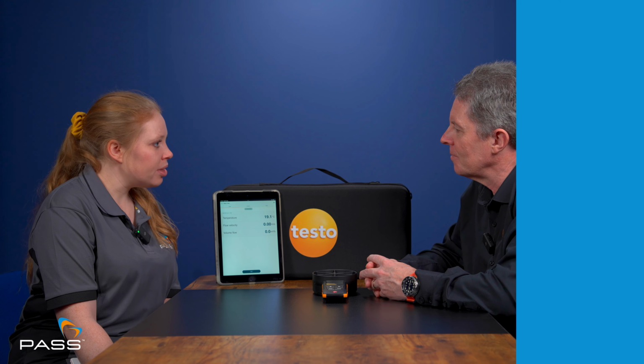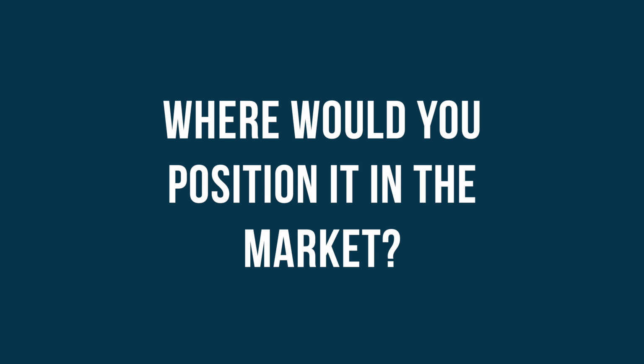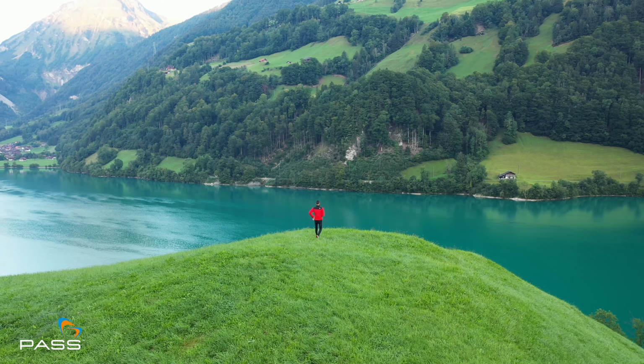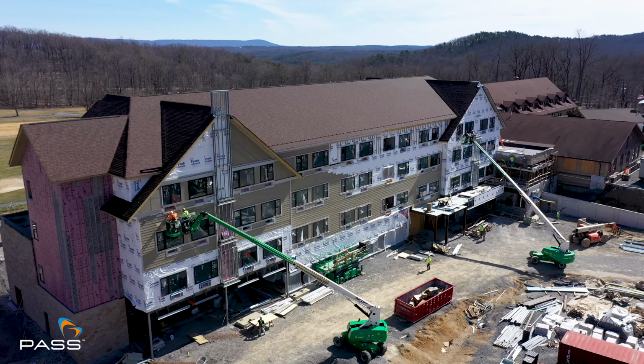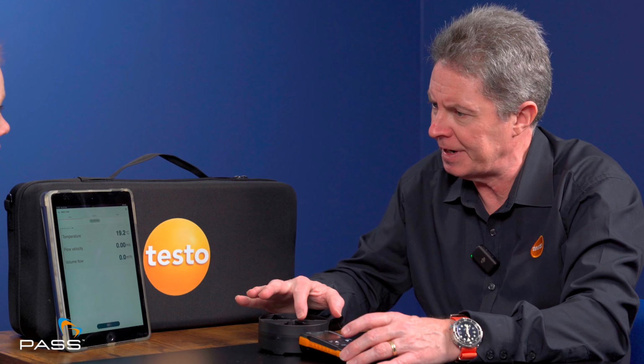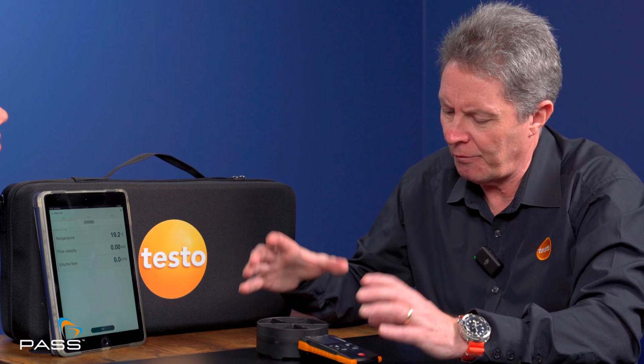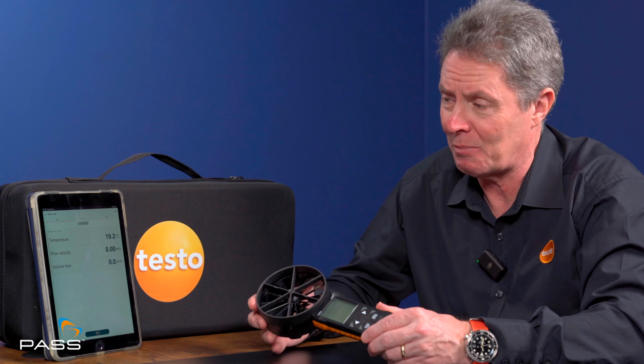Considering the Testo 417 vane anemometer's testing capabilities, where would you position it in the market? If you look at vane anemometers generally, you can buy very low-cost ones for less than £100. These are typically used not so much by proper ventilation engineers but by hobbyists - even hill walkers checking wind speeds before going out, or people hiring cherry pickers checking wind speed isn't too high. But lower-cost anemometers have a much smaller vane, so you don't get any real accuracy. As a minimum, a 100mm vane is seen as the benchmark in the ventilation testing market to get high accuracy.